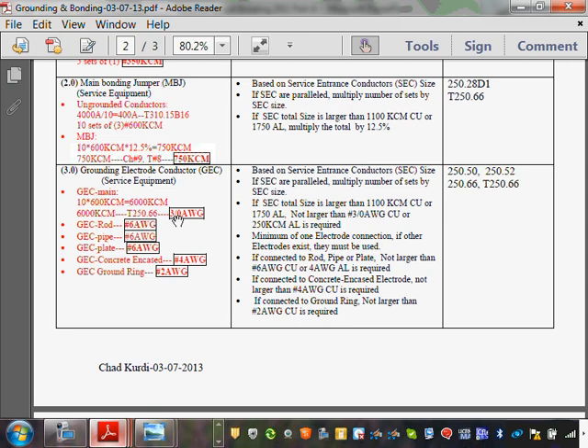If you pull all phase A, 10 conductors of phase A, imagine putting them in a conduit. Number 1, you almost can't do that in one conduit. But if you put all 10 conductors of phase A in one conduit, all the conductors of phase B in one conduit, and C in one conduit, 10 of them, then the neutral can be alone in one conduit. Then when we size the neutral at the top, you don't have to divide by 10. The size of your neutral will be 750.